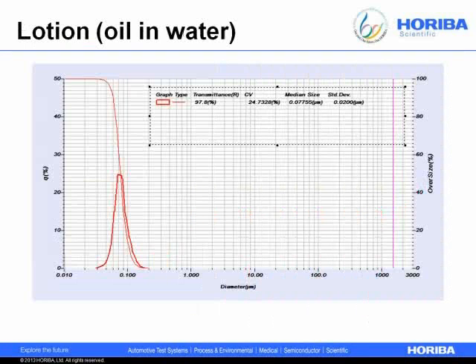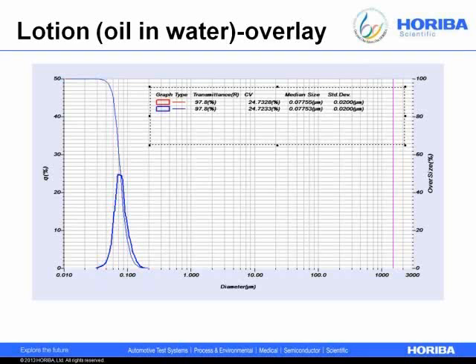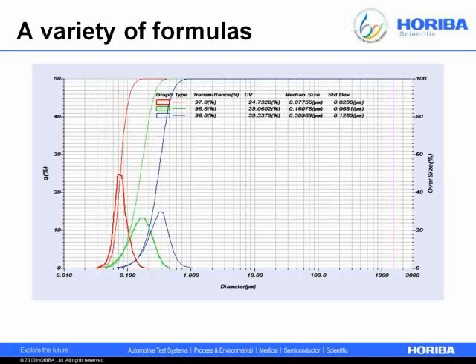For an oil-and-water lotion emulsion, the differential size distribution shows sizes well below 100 nanometers — around 80 nanometers. Three repeats give an almost exact overlay of the curves; the median size changes only in the fourth decimal place. We can also compare a variety of lotion formulas, plotting diameter on the x-axis with the differential distribution on the left and cumulative distribution on the right.